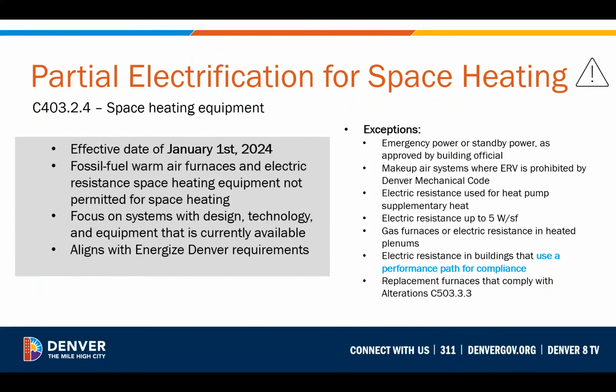This is a mandatory requirement per that exclamation mark in the top right. So it does not matter if you're complying prescriptively or through the performance pathways, you will need to comply with this. There are several exceptions that you can see on the right of the slide here. Some notable ones being emergency power, makeup air systems where you cannot do an ERV due to the Denver Mechanical Code. You can use some electric resistance, as you can see, but it can't be the primary source of heating.